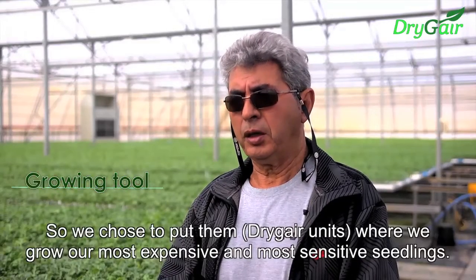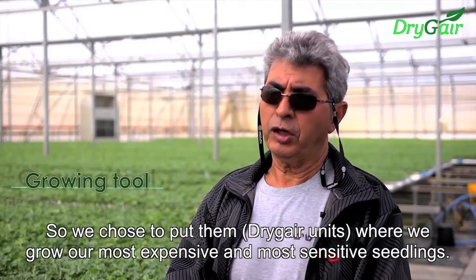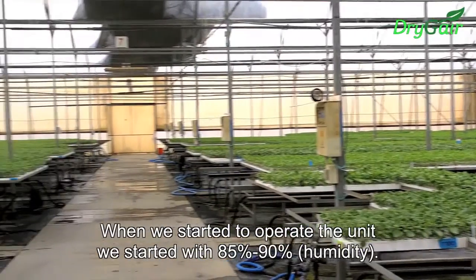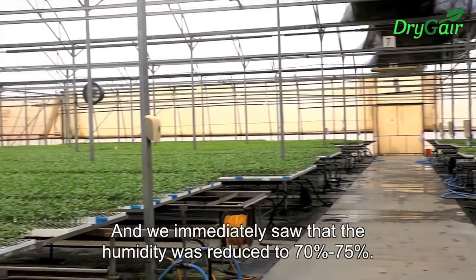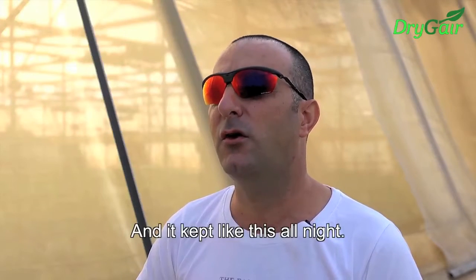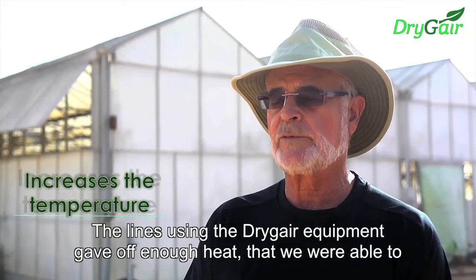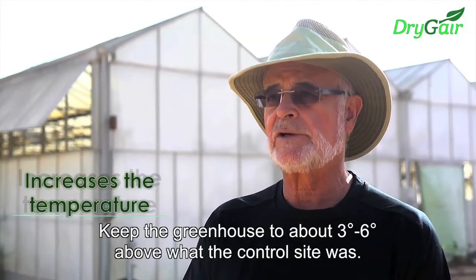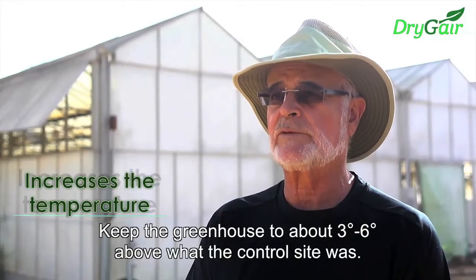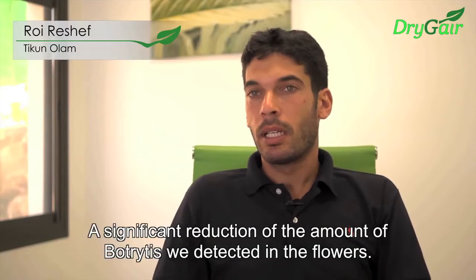When we started to operate the unit, humidity started at 85–90% and we immediately saw it reduce to 70–75%, and it kept like this all through the night. The Drygair equipment gave off enough heat that we were able to keep the greenhouse 3 to 6 degrees above what the control side was. It had a significant effect on the amount of Botrytis.